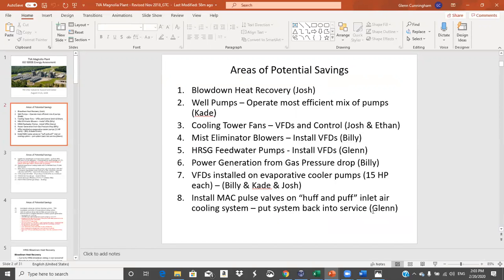So if I take 0.6 and cube it, because the affinity law says power drops with the cube, 0.6 cubed is 0.216. And I'm going to operate 5 of those, and each one is 200 horsepower. Because 200 times 5 is 1,000, times 0.216. Even I can do that in my head. So that's 216 horsepower, and I get my 60% capacity. So would you rather pay for 600 horsepower, or would you rather pay for 216 horsepower? That's pretty obvious.